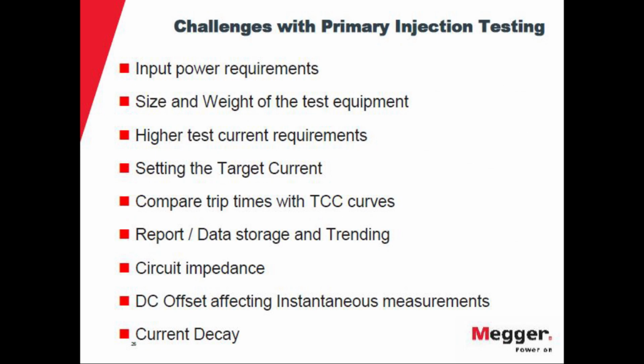In addition to the manual way to test, there are other challenges. One is the input power requirement. Sometimes you need very high power to do the testing. The primary current injection test sets are not generators. Whatever you put on one side of the instrument, it transforms into a higher current but a very low voltage. Sometimes it's not the instrument, it's the power supply that needs to be in good shape to provide a good signal so the instrument can run the test. Because it is basically a transformer inside, it's always going to be heavy equipment of a good size.